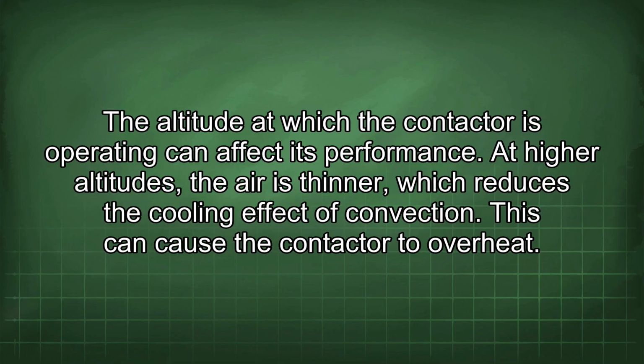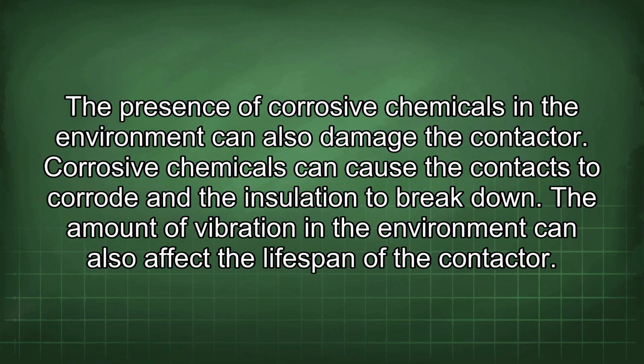The altitude at which the contactor is operating can affect its performance. At higher altitudes, the air is thinner, which reduces the cooling effect of convection. This can cause the contactor to overheat. The presence of corrosive chemicals in the environment can also damage the contactor. Corrosive chemicals can cause the contacts to corrode and the insulation to break down.